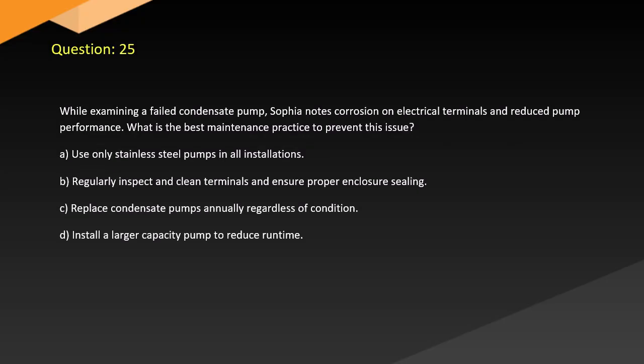Question 25. While examining a failed condensate pump, Sophia notes corrosion on electrical terminals and reduced pump performance. What is the best maintenance practice to prevent this issue? A. Use only stainless steel pumps in all installations. B. Regularly inspect and clean terminals and ensure proper enclosure sealing. C. Replace condensate pumps annually regardless of condition. D. Install a larger capacity pump to reduce runtime.